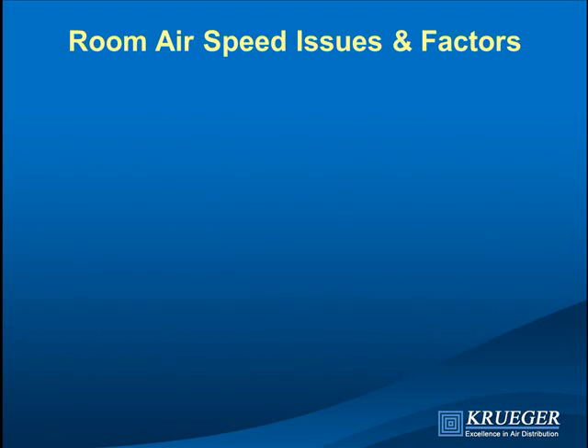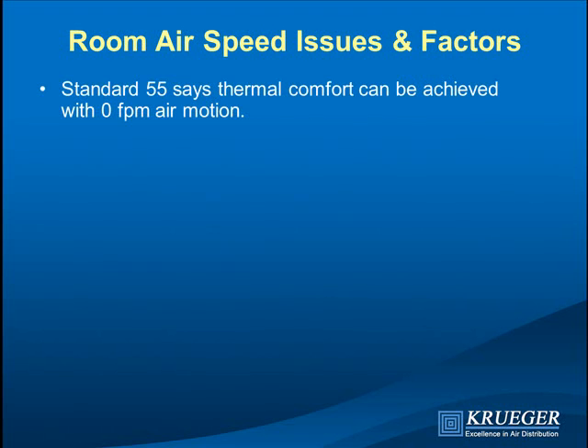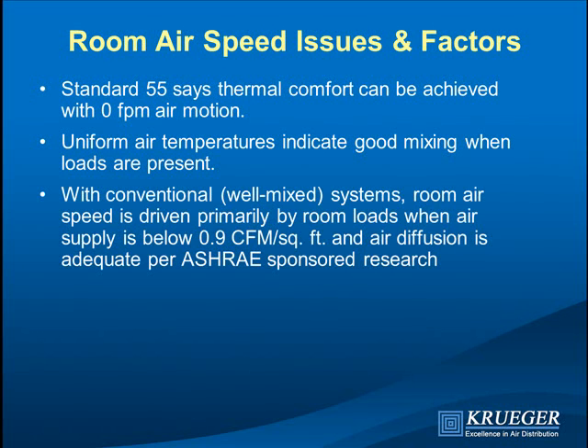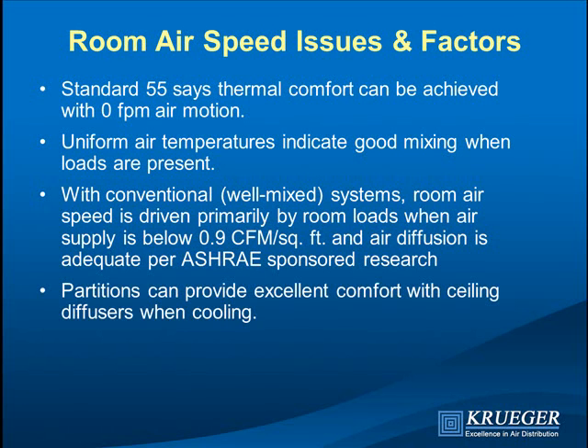ASHRAE Standard 55 has said for 30 years there is no minimum airspeed for comfort — if you have uniform air temperatures, everything is working. With well-mixed ceiling diffusers, at less than 1 CFM per square foot, average room airspeed is a function of the space load, not the diffuser air supply. So the myth that constant volume systems provide higher air motion than VAV systems doesn't hold up. At low loads, both have fairly low room air motion. Partitions, tested extensively in the 1970s, actually assist ceiling diffusers when set up properly.